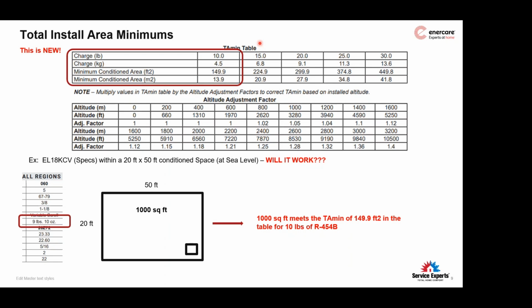This TA minimum table, you're going to find it or something like it, depending on the manufacturer, on the indoor coil. There'll be a sticker on it. It's also in the manual, of course. This is where I pulled this from, but there's going to be a sticker on the front. Carrier uses a multiple: for every pound of refrigerant, you multiply by 15 for your minimum square footage.